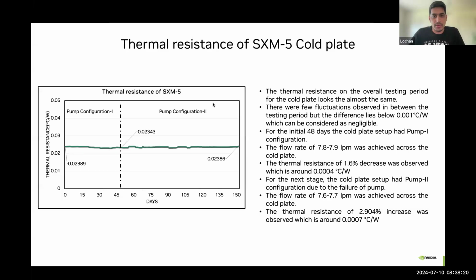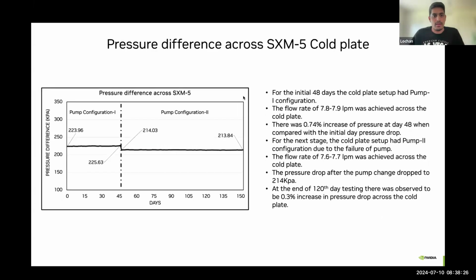Coming to the pressure drop. Pratik, next slide, please. Looking at the pressure drop across the cold plate, for the pump one configuration during the initial 48 days of testing, the average pressure drop per day was measured at around 224 kPa. At the end of testing, it was 225.6, almost 1.6 kPa of difference.